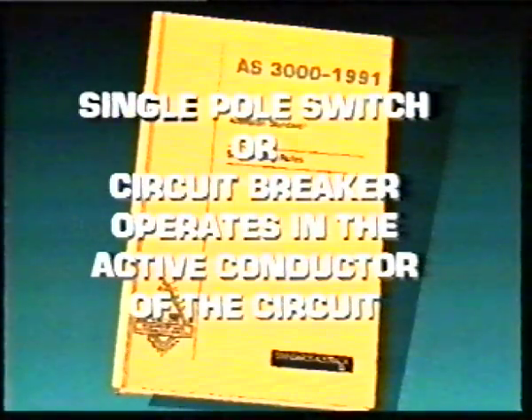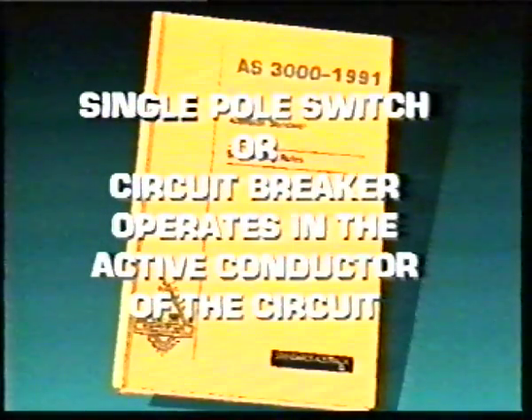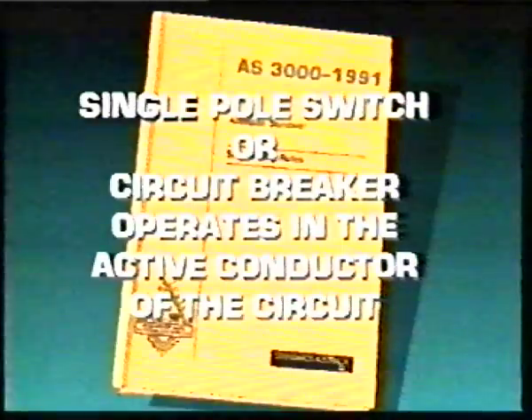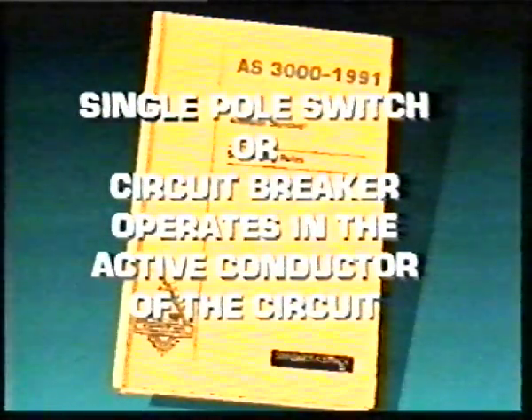This test is necessary because an incorrect connection of active and neutral conductors to accessories and equipment is extremely dangerous and has been the cause either directly or indirectly of many shocks and fatalities. People expect that a circuit or an appliance plugged into a socket outlet is disconnected from the supply when the control switch is in the off position. When the polarity is incorrect, parts such as heating elements and lamp holder terminals are live and extremely dangerous. AS3000 generally requires that every single pole switch or circuit breaker operates in the active conductor of the circuit in which it's connected, and that switches or circuit breakers of multi-phase circuits operate simultaneously in all active conductors.